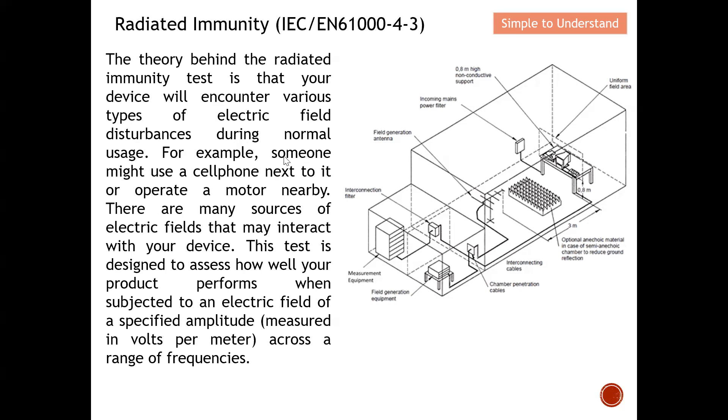Someone might use a cell phone next to it or operate a motor nearby. There are many sources of electric fields that may interact with your device. This test is designed to assess how well your product performs when subjected to an electric field of specific amplitude, measured in volts per meter, like 3 or 10 volts per meter across a range of frequencies.